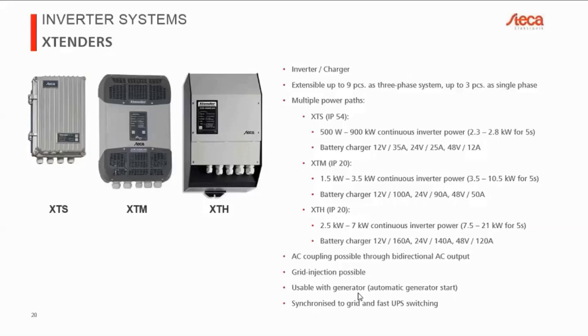We can do much more than with a SOLARIX PLI. We can program the contact for certain time slots. We can program them to give you maybe an alarm status, all sorts of things. There are several hundred parameters we can program on the extenders, as opposed to the SOLARIX PLI, where we have about 35. And then finally, this is very similar to the SOLARIX PLI. We can synchronize to the grid and have fast UPS type switching. So again, 10 to 20 millisecond switching time.